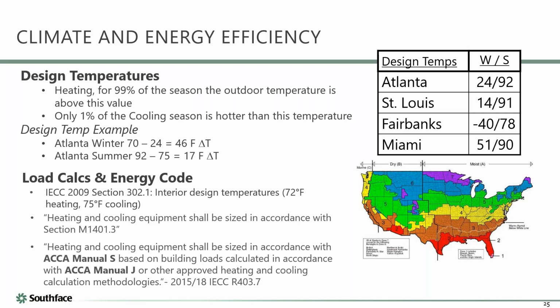It's not necessarily that. But what happens is they look at the statistical weather for a city and they go, okay, there's a temperature value outdoors at which it's only colder than that 1% of the hours. So about 25 hours of the year, it's colder than 24 degrees on average in Atlanta. And likewise, in Atlanta, it's only 1% of the hours, about 25 hours out of the summer on average, that it is hotter than 92 degrees outside. So we're using the almost hottest day and the almost coldest night of the year as our outdoor design temperature. And then we get a delta T across it: the 70 minus the outdoor design temperature, and the 92 minus the indoor design temperature. Those are the delta Ts that get used when we do a load calc.